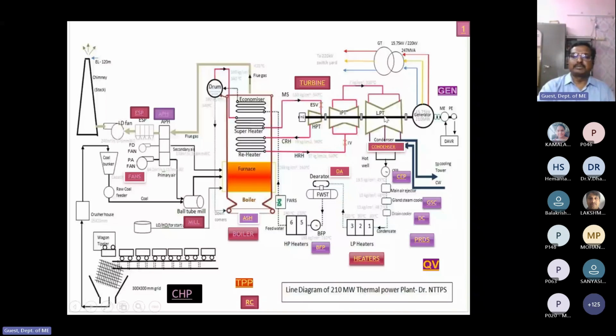The purpose of using many turbines is compounding. To extract the energy available in the steam, if you use a single turbine, it will be very big. It will cause vibrations, and maintenance and operational problems will also occur. That is why we share the energy. That means we convert the energy in a number of stages, in a number of turbines. So in this design we have three turbines: HP turbine, IP turbine, and LP turbine. After the LP turbine, the steam goes to the condenser and comes back to the boiler. We will go one by one here. The turbine.